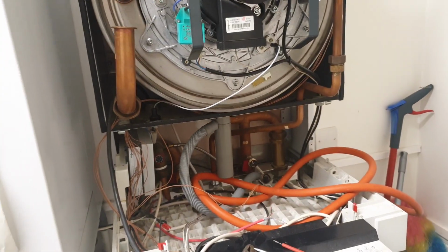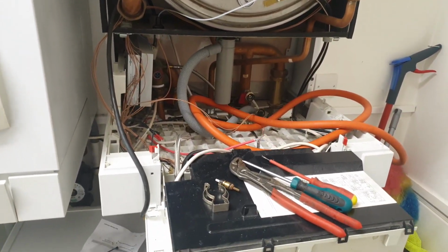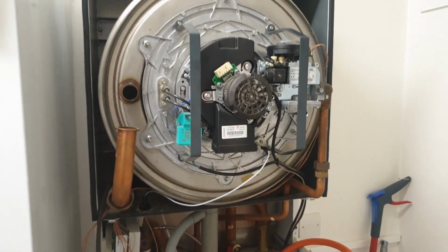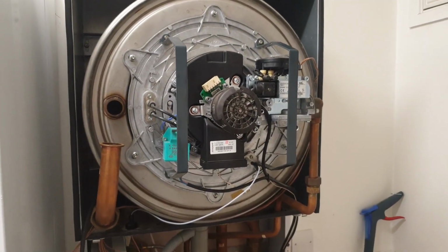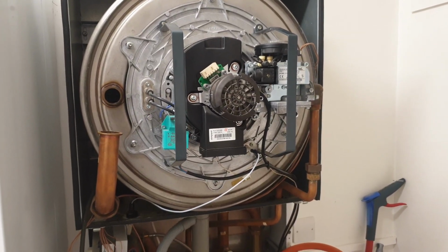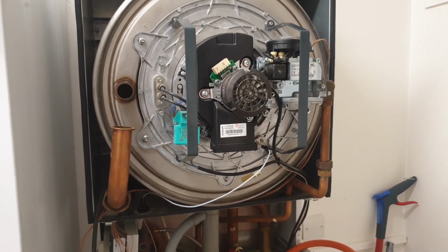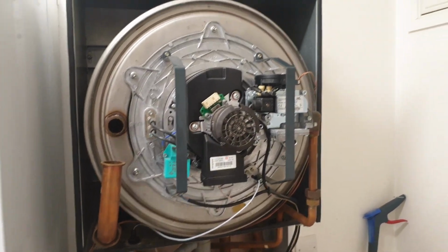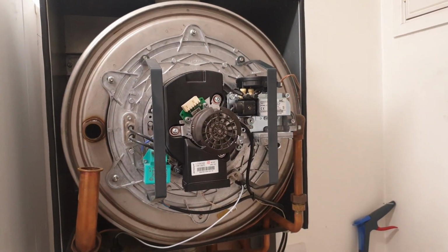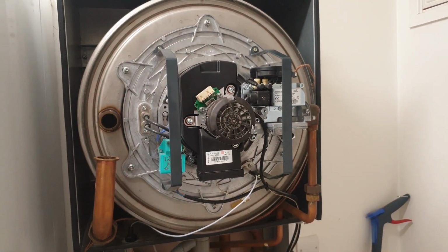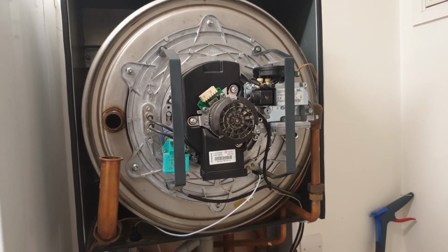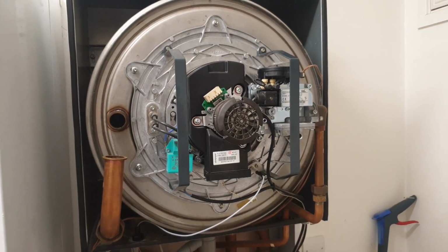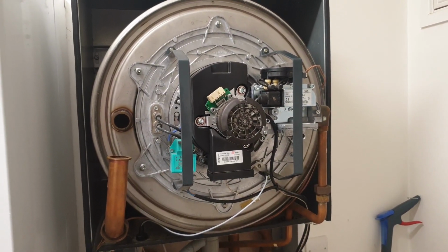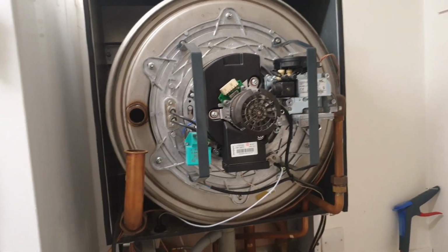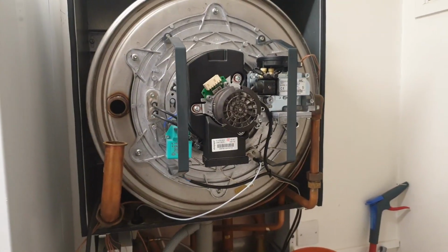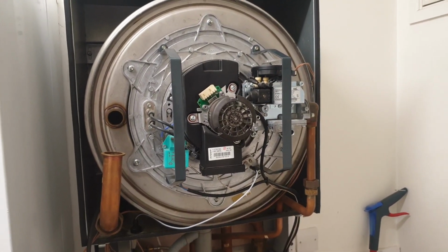Now, to protect boilers from this scaling process, I've been using plate separation for quite a while on any jobs where I see a problem. So a plate heat exchanger prevents any of the water in the boiler originating or coming back from the heating system itself. And that's been very, very successful. Now, the interesting part of that, and it backs up my idea about this localized overheating within the heat exchanger, is that I don't see those plates getting blocked up. I've never had to clean a plate heat exchanger on any of the systems where I've used plate separation.